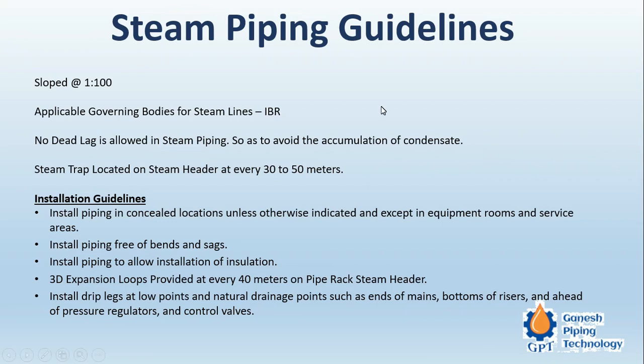Steam lines are normally sloped at a ratio of 1:100. The applicable governing body for steam lines is IBR. Dead legs are not allowed, because if there is a dead leg — where the pipe goes down and then back up — condensate accumulates in that dead leg and is not acceptable. Steam trap locations on the steam header are required at every 30 to 50 meters.